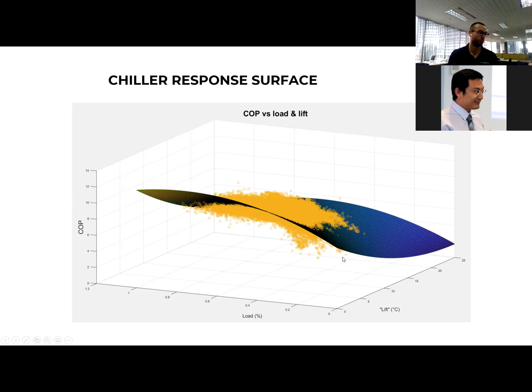But this is showing the COP of one of those high load chillers. I think this was chiller 6 in the system. It's showing the COP as a function of part load and lift. For this project, unfortunately, we didn't have condenser water temperatures. Those trend logs weren't available, so we've used a pseudo lift here of outside wet bulb minus the leaving temperature set point. This was just to give us an idea of how the chillers are responding to a change in condenser water leaving temperature.